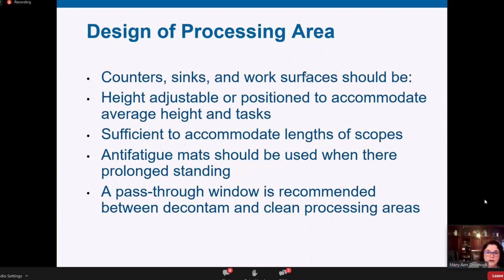Best practice would be to not have storage even in the AER room, even though it's considered your clean processing area, because those scopes are dirty coming in there. They've only been cleaned—that doesn't mean they've had a terminal process on them. So best practice would be to not have it in there.